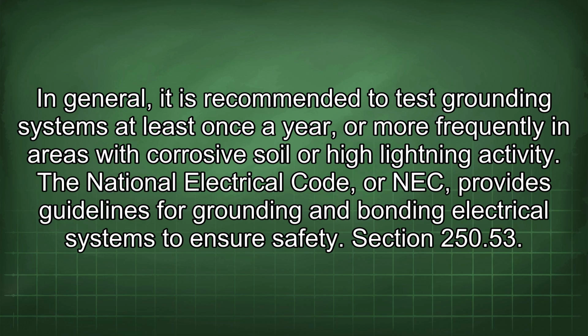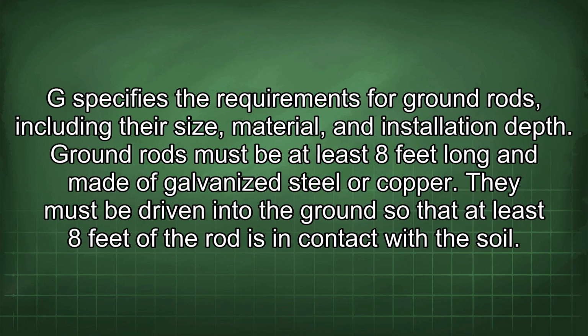The National Electrical Code, or NEC, provides guidelines for grounding and bonding electrical systems to ensure safety. Section 250.53 G specifies the requirements for ground rods, including their size, material, and installation depth. Ground rods must be at least 8 feet long and made of galvanized steel or copper. They must be driven into the ground so that at least 8 feet of the rod is in contact with the soil.